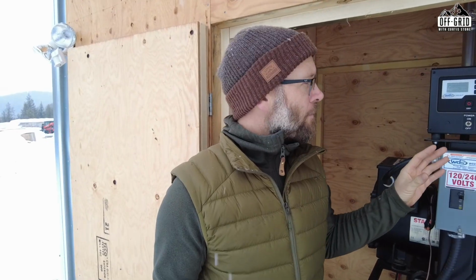So this system has 3 triggers that would go in sequence. The bottom trigger is if the batteries hit 48.5 volts for more than a minute, the generator will kick on. Above that, if the batteries go down to 49 volts for an hour, the system will kick on. And then on the top, I believe it's 49.5, if the batteries are sitting at 49.5 volts for 24 hours, it'll kick on. So there's kind of 3 gates you'd go through.